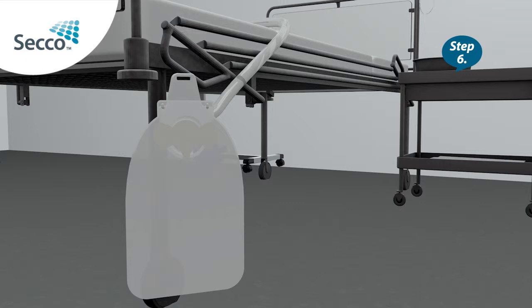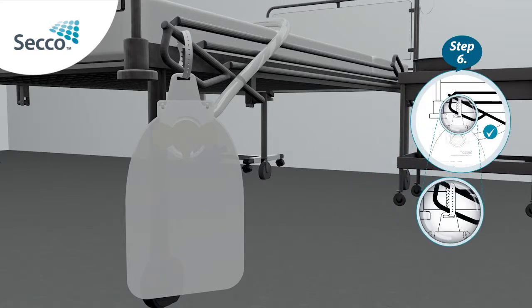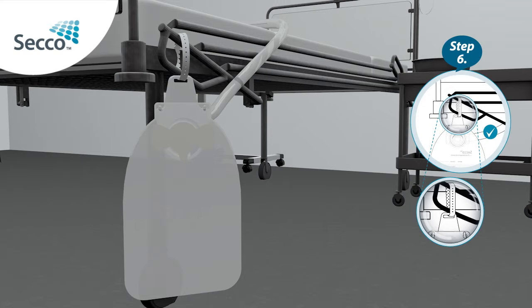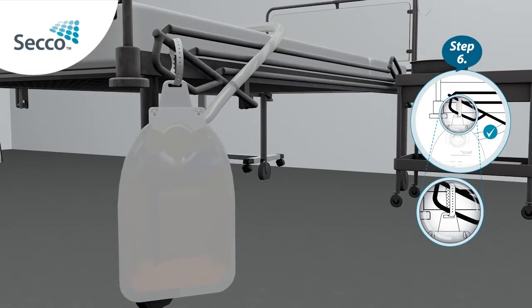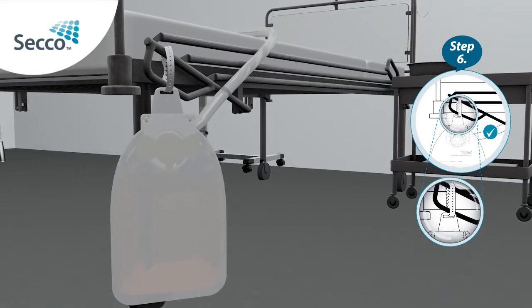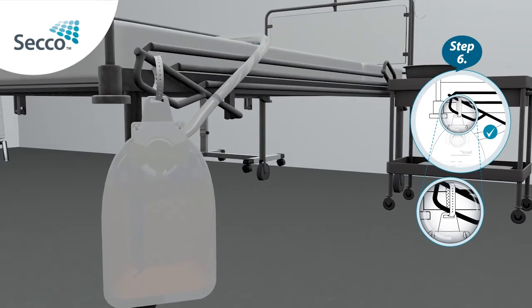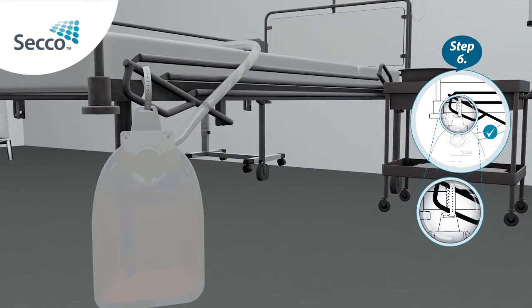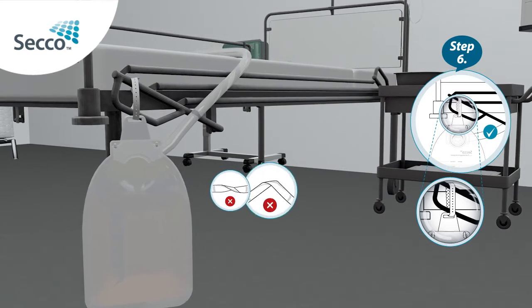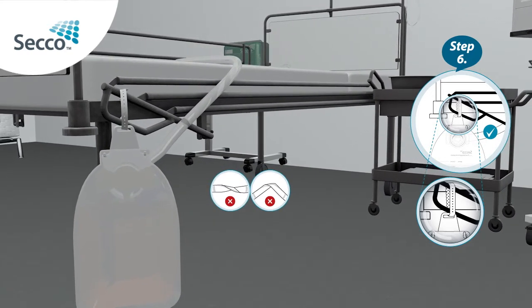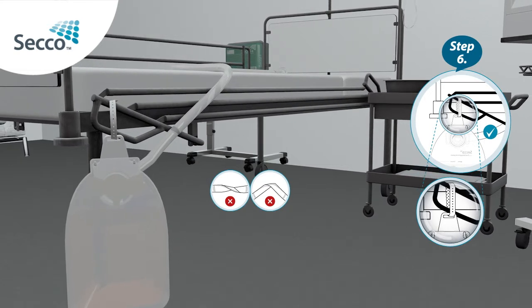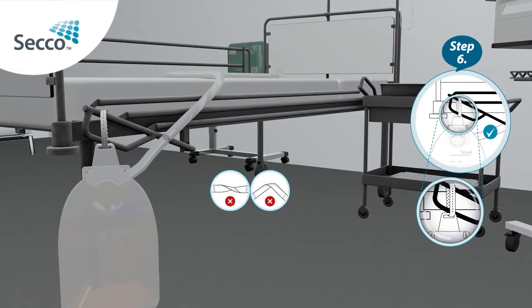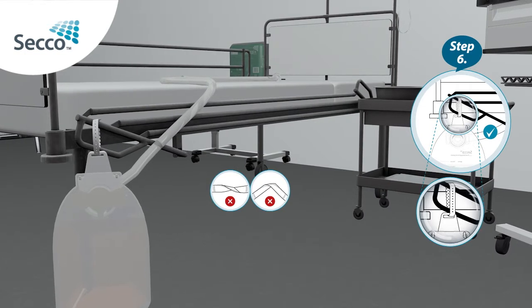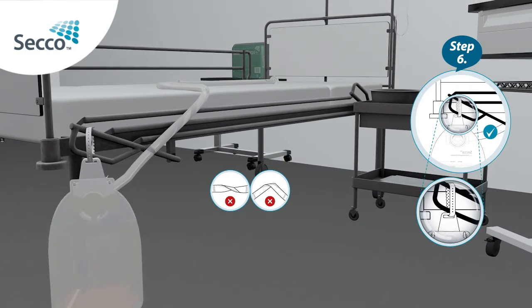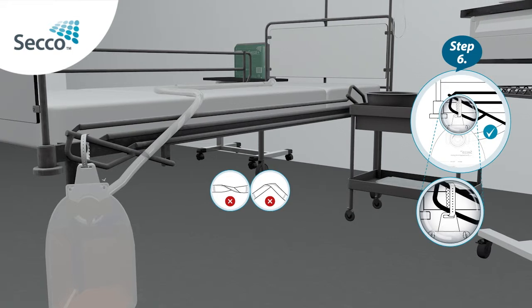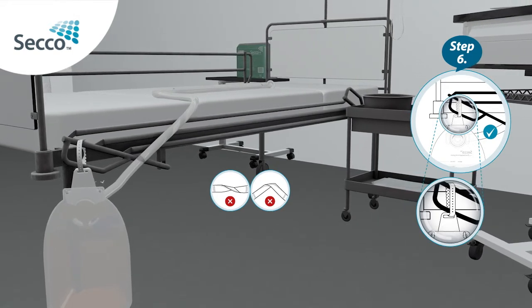Step 6. Attach the strap onto the lower bed frame at a position lower than the patient will be lying to ensure waste flows downwards with gravity. Make sure it is attached without twisting or kinking the catheter. Note the silicone tube at the joint to the mounting plate may be slowly and carefully rotated to remove any twists in the tube after the patient has finally been settled.